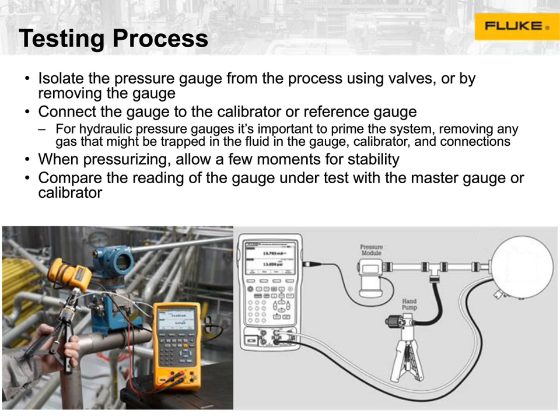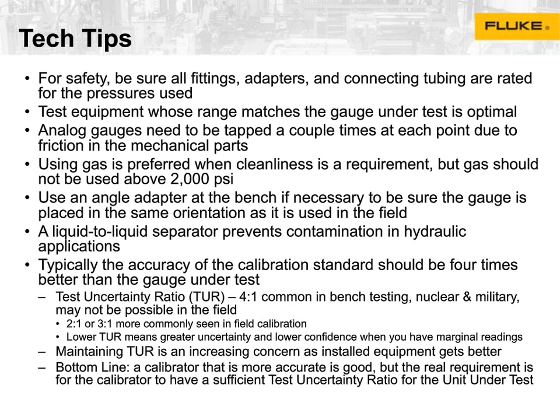There's less piping, there are fewer connections, there's less chance for leaks. The simpler you can make your test setups, the better your results will be. All right. So again, this is a fairly simple procedure, so I'm not going to spend a ton of time on it. But the technician tips: one of the things we see a lot of is people will have one rig that they set up in their truck, and they may or may not have actually looked at whether the fittings and tubing are rated properly.